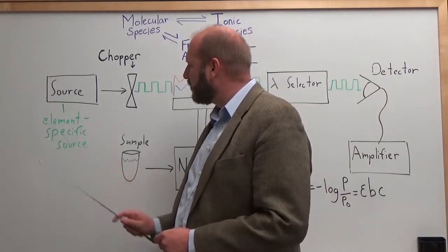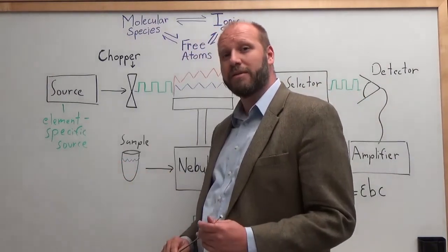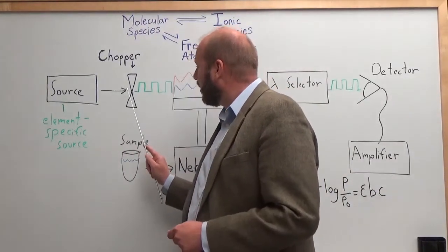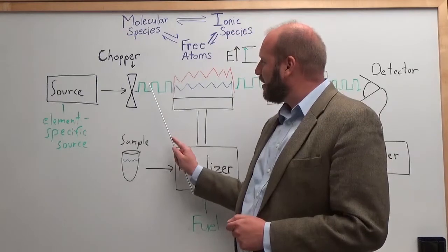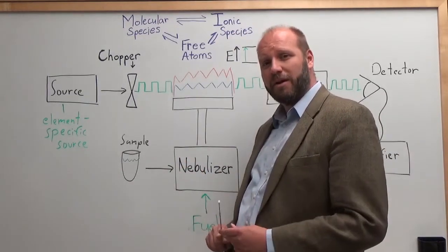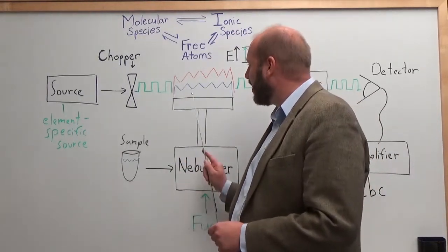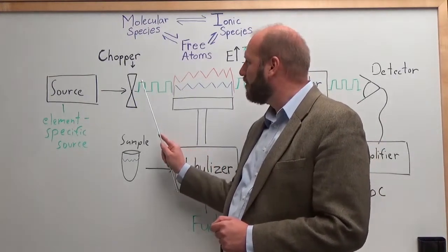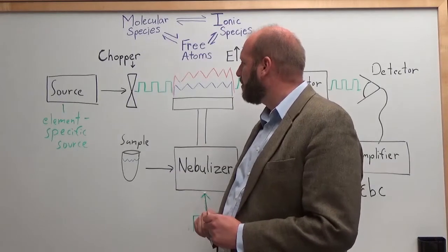So, if we look at our element-specific source, it has one wavelength of interest that we want to measure the absorption from. We put it through a chopper and what the chopper does is have that light turn on and off at a given rate. We turn it on and off because our flame is a light source itself and we need to be able to tell when we're measuring light from our sample versus from the flame.